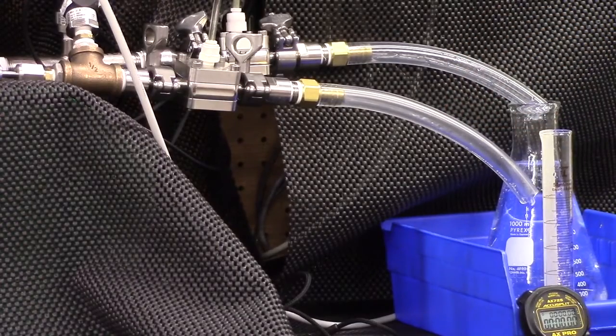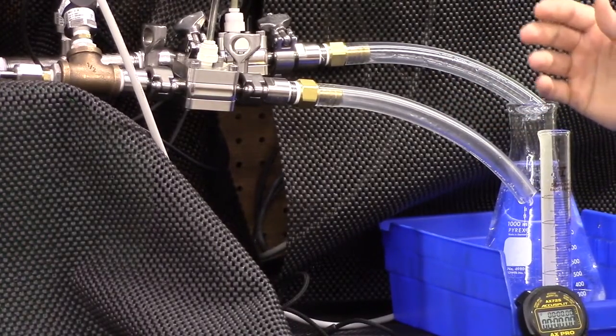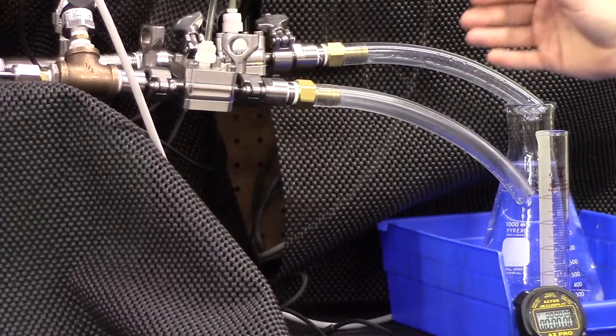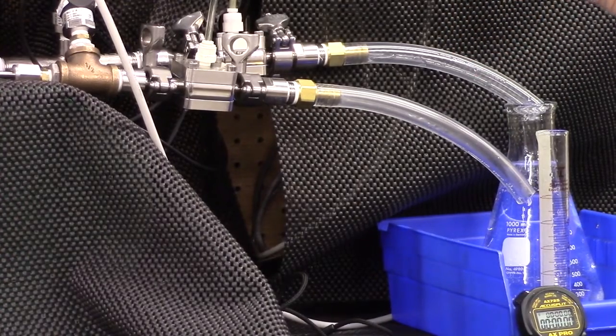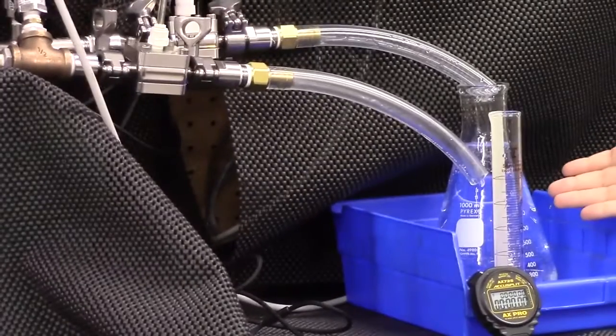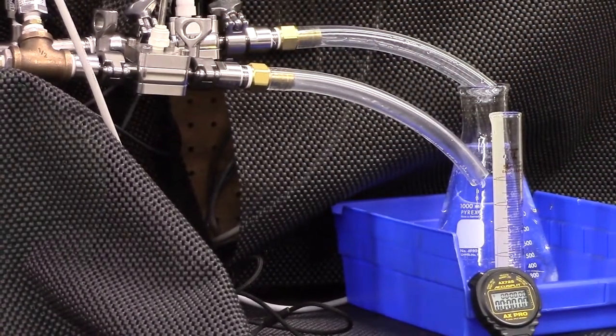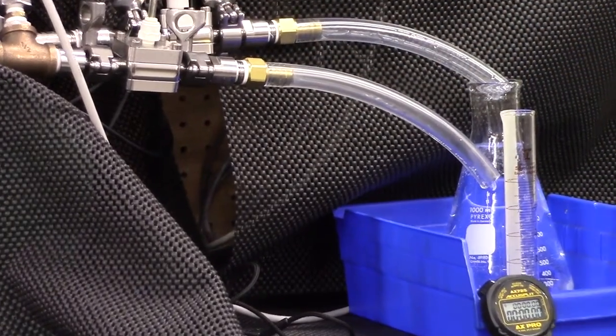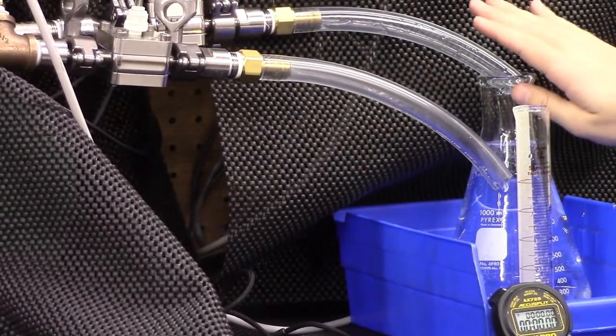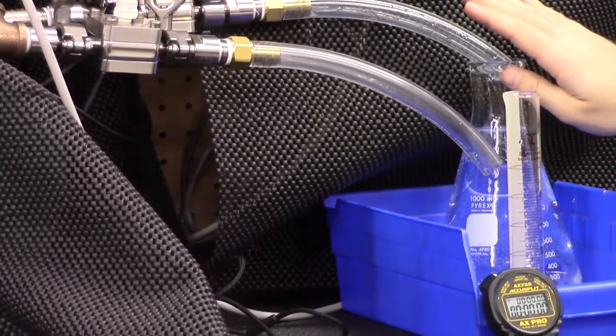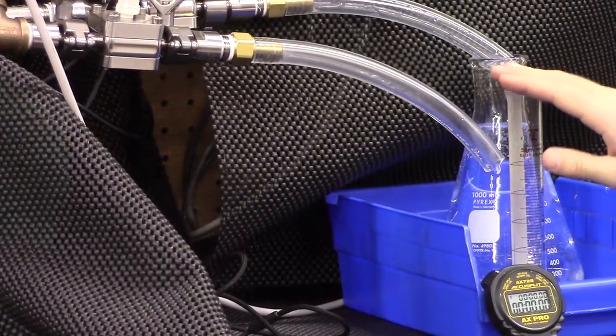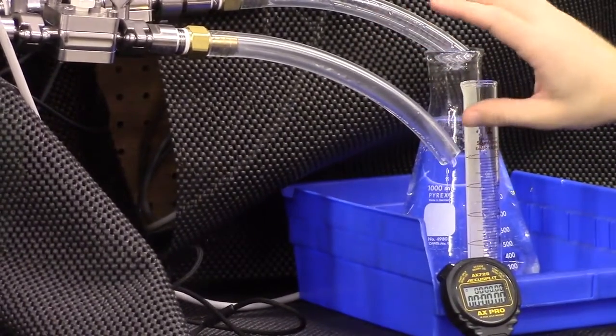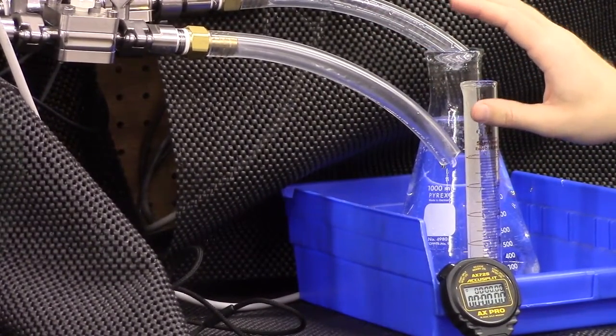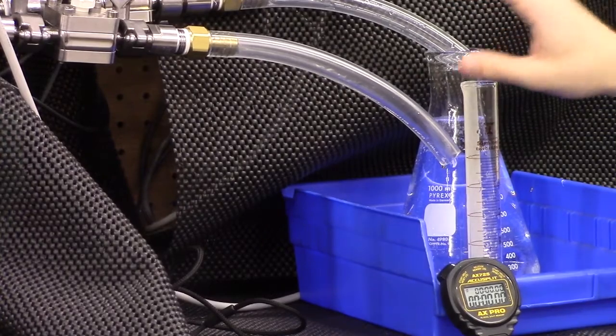In a typical inline conditioning system, like we stated earlier, this would feed a supply pump or your skid downstream. In this case, we're going to use two different volumetric containers, comparing these two identical back pressure regulators at a 100-to-1 flow turn down. So in one regulator, we're going to look for a 1,000 milliliters per minute flow rate, and then in the other back pressure regulator and flow control system, we're going to look for a 10 milliliters per minute flow rate. So we will go ahead and start the system up now.